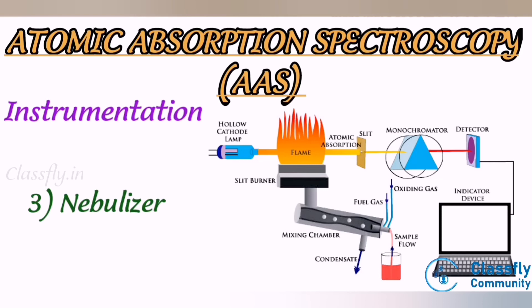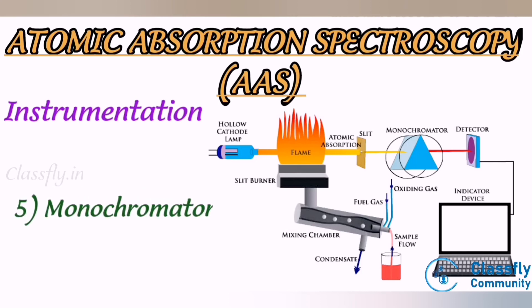Third, nebulizer: it sucks up a liquid sample at a controlled rate, creates a fine aerosol spray for introduction to the flame, and mixes the aerosol with fuel and oxidant for introduction to the flame. Fourth, detector: a light selected by the monochromator is directed onto a detector — typically a photomultiplier tube — which converts the light signal into an electrical signal proportional to light intensity, processed by a signal amplifier. Fifth, monochromator: used to select the specific wavelength of light absorbed by the sample and to exclude other wavelengths.